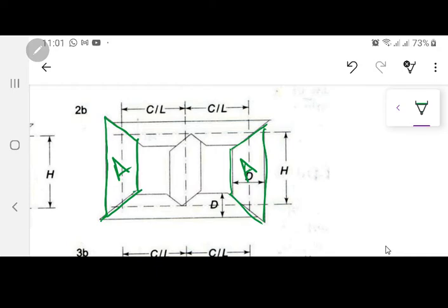So in practical terms, listen to this very carefully. If this is shape A over here, I am going to add another lamination on this one, then I am going to add another one. In this way you are going to stack up laminations, with a little bit of size decrease, and make a circular stepped core.